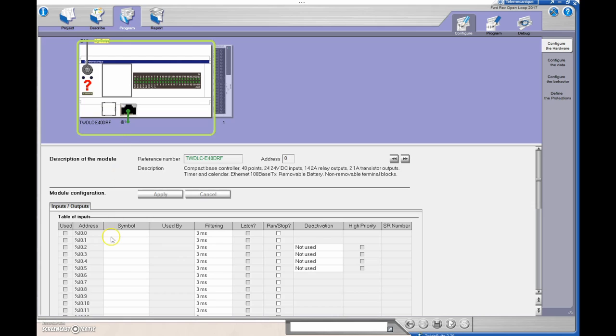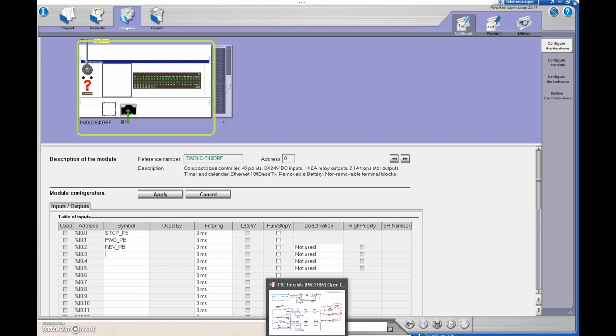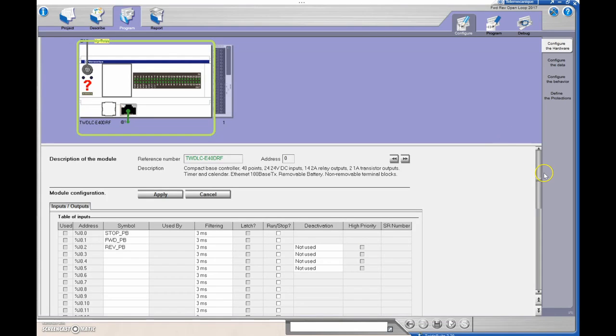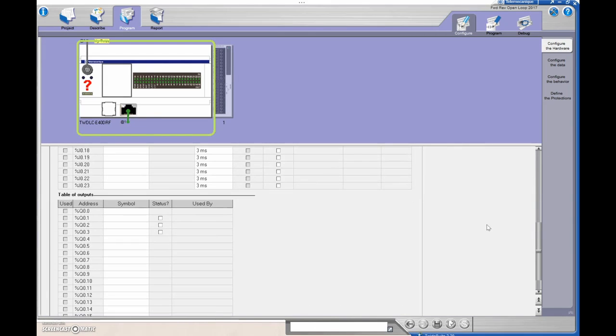Now we're going to set our IOs. Our first input is our stop push button, then we've got our forward push button and our reverse push button. We're getting those from our diagram — stop is zero, forward is one, and reverse is two. Our outputs Q2 and Q3 are the forward and the reverse, so Q2 and Q3 will be listed below.